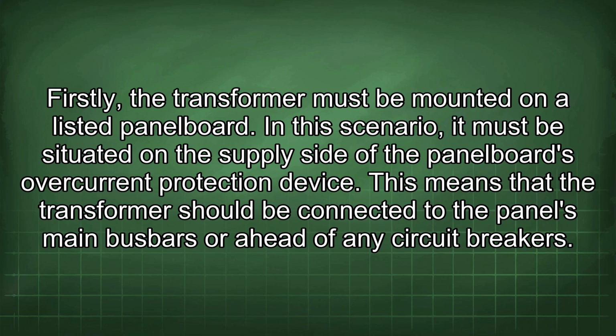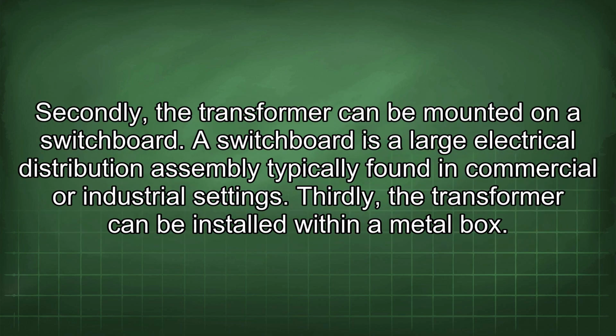Firstly, the transformer must be mounted on a listed panel board. In this scenario, it must be situated on the supply side of the panel board's overcurrent protection device. This means that the transformer should be connected to the panel's main busbars or ahead of any circuit breakers. Secondly, the transformer can be mounted on a switchboard. A switchboard is a large electrical distribution assembly typically found in commercial or industrial settings.